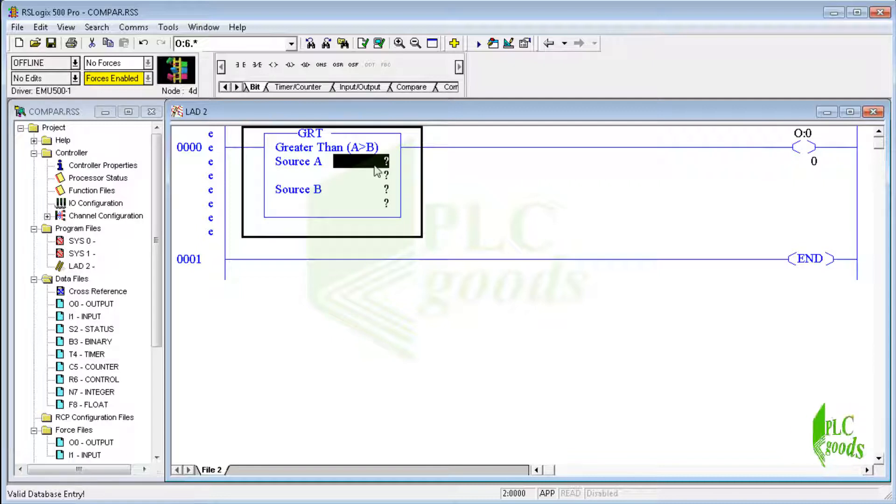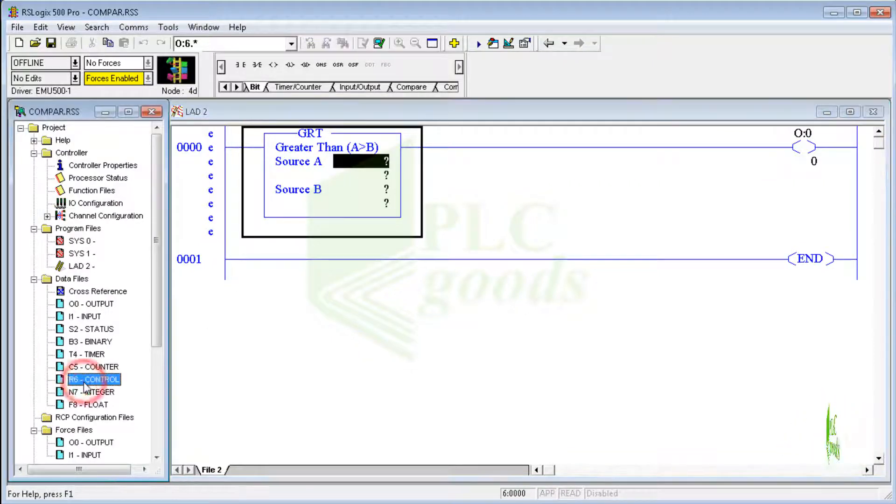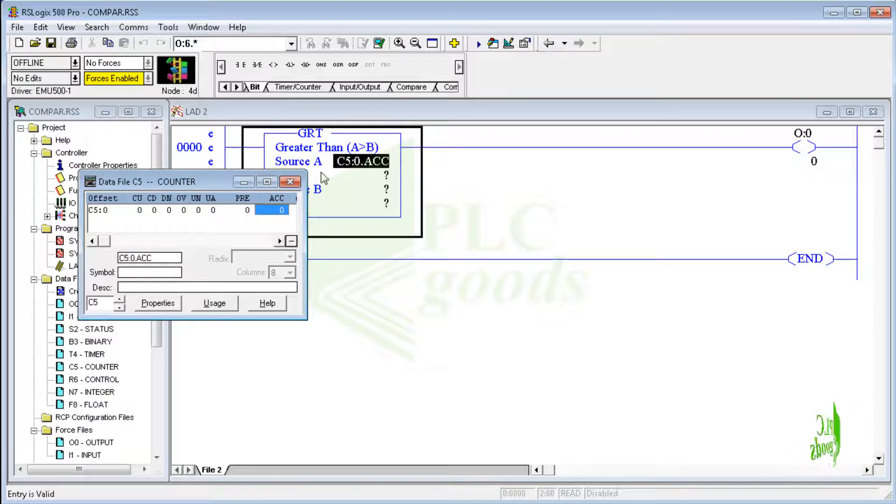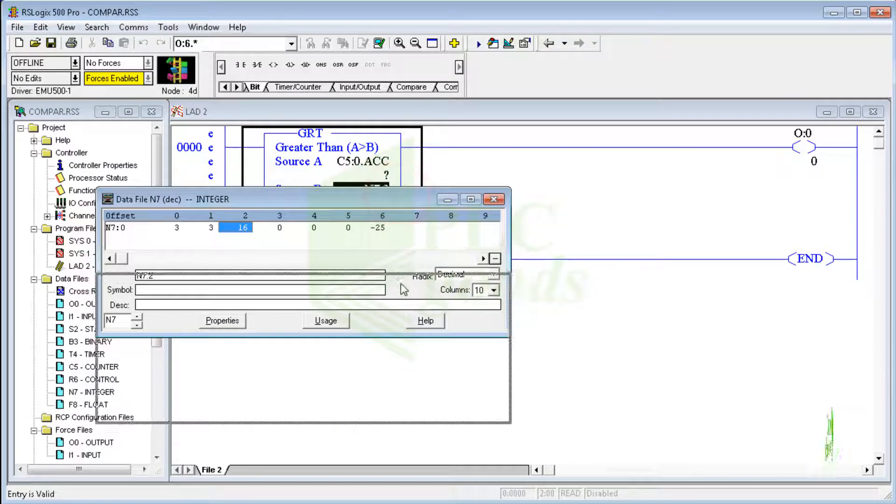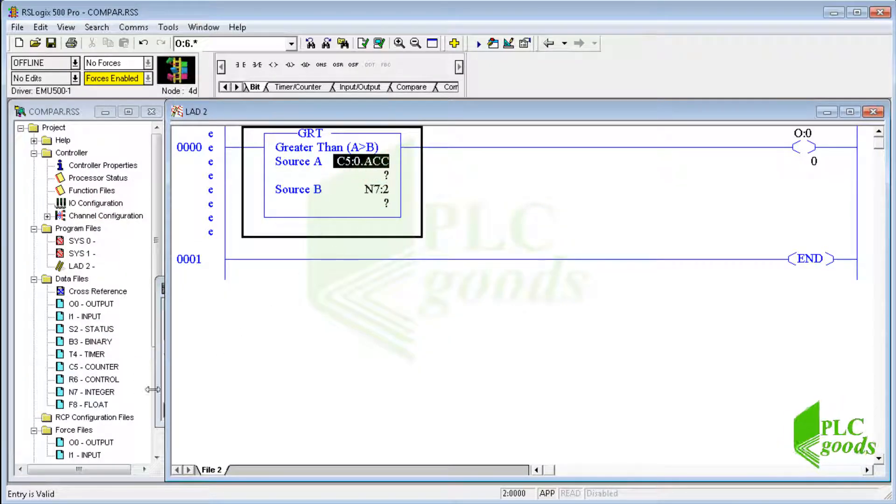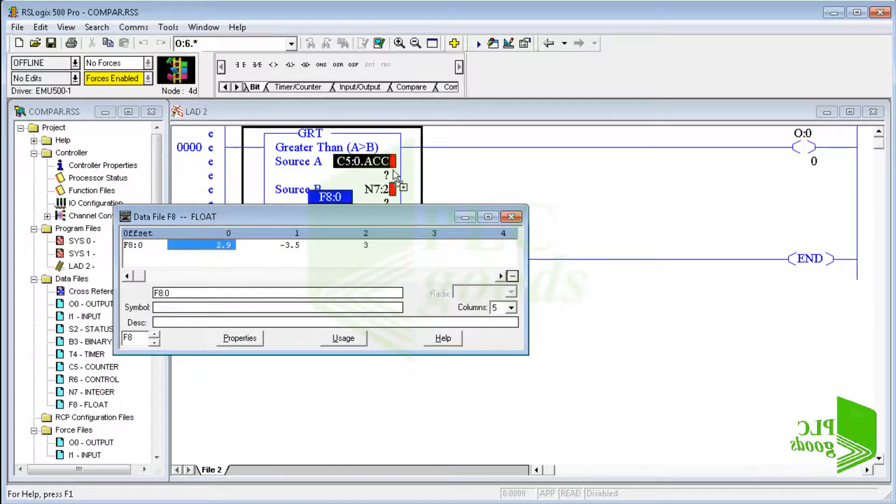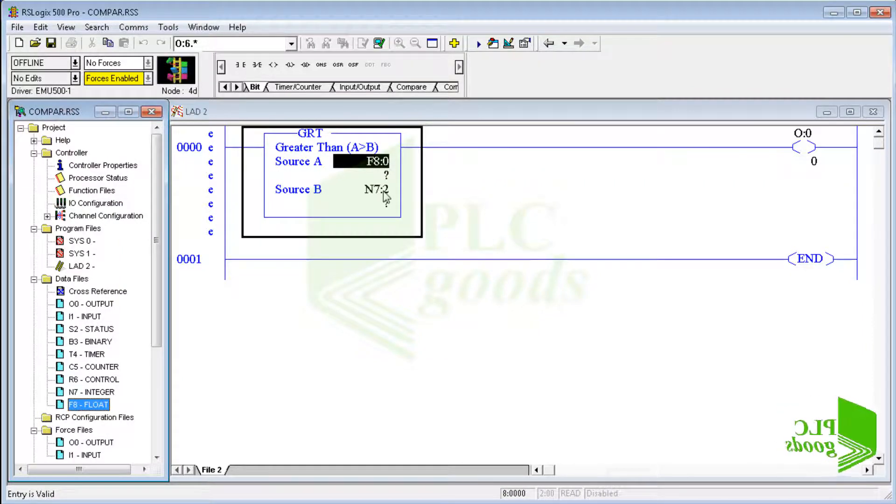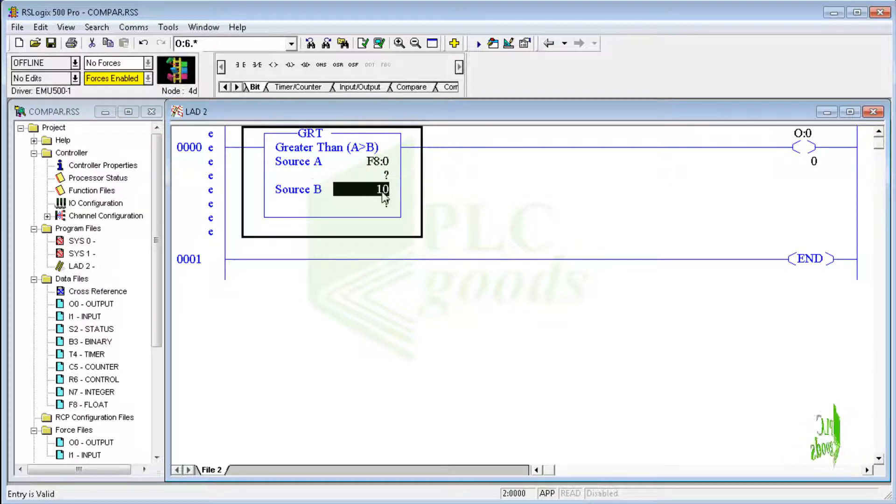Source A is the address of any data which contains some value, for example numbers in the counter file that are stored as preset value or accumulated value. Similarly, source B can be either a constant number or a word address which is used to store a number. As you see, I can change this address and use another address easily. Now the first number in the float data file with F8:0 address is compared with the integer number which was stored in N7:2 address. Also, I can use a constant number for source B.